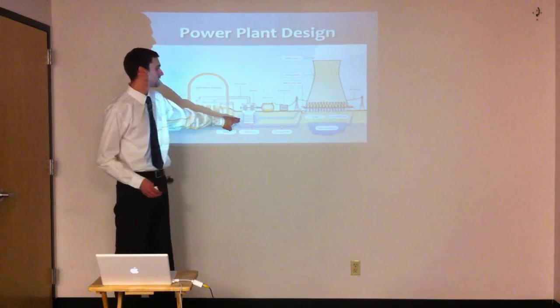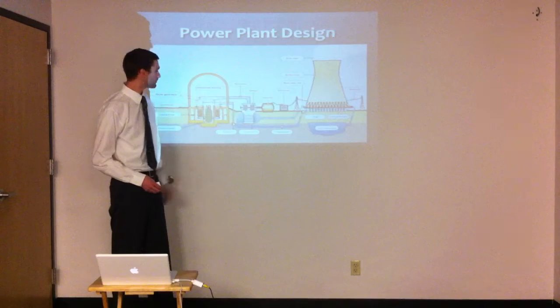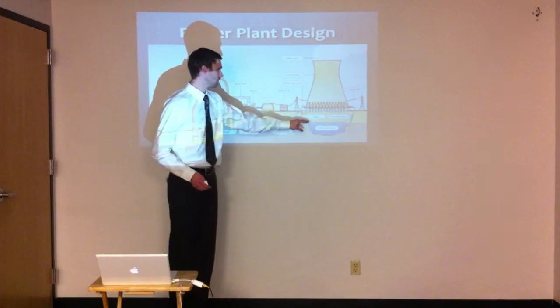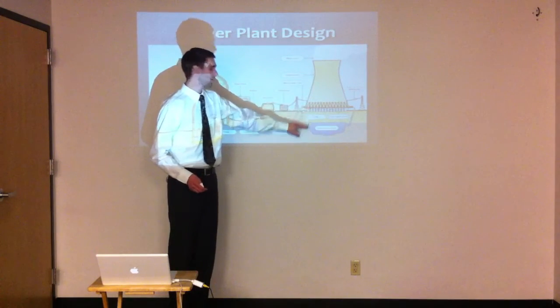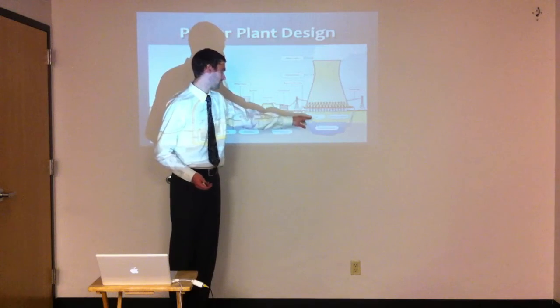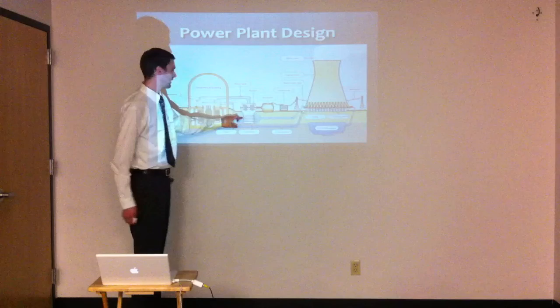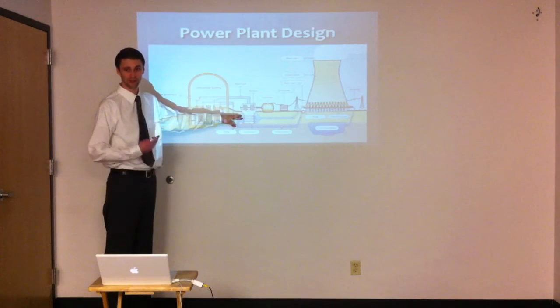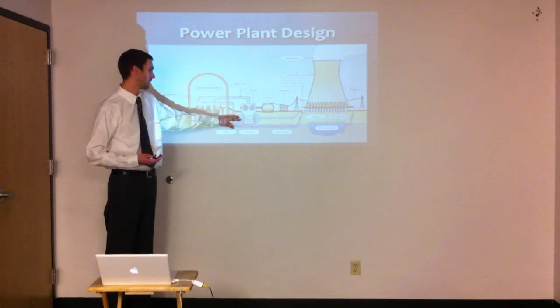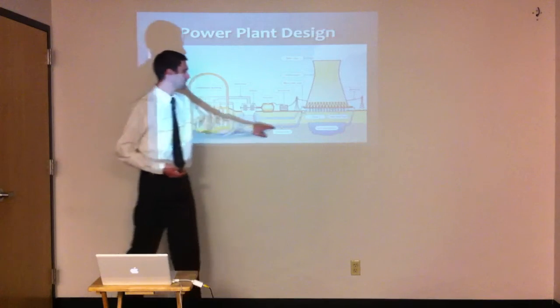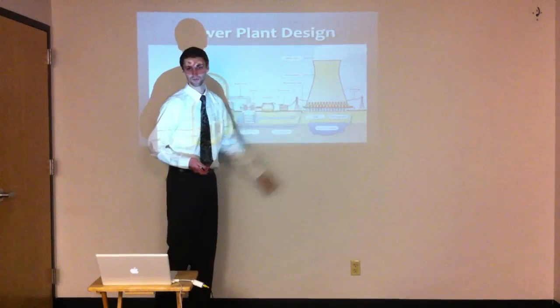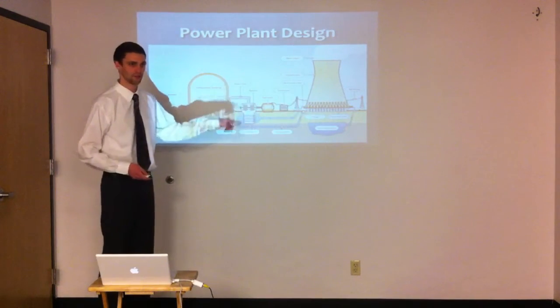Now the condensing system has its own water system, and it brings in cold water from this cooling tower or from some other natural source. Then it's brought through this condenser, and as that happens, this water heats up because of being in contact with that steam. Then they run it back to this cooling tower to be cooled. And so that cycle just continues also.